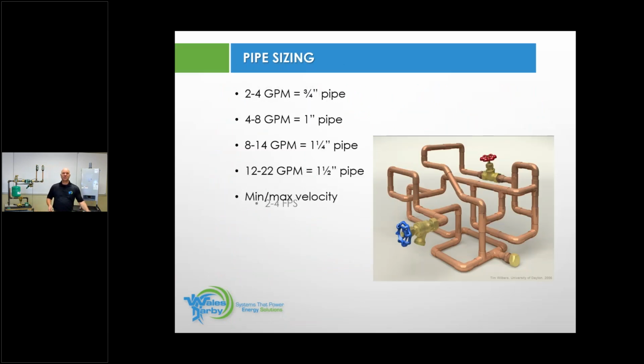Again here, this is just giving you your flow rates and minimum and maximum velocities. And what do we mean by that? We need to move water at a certain rate within that pipe. And our goal is 2 to 4 feet per second. We do not want to really exceed the 4 feet per second because we'll get into other things.